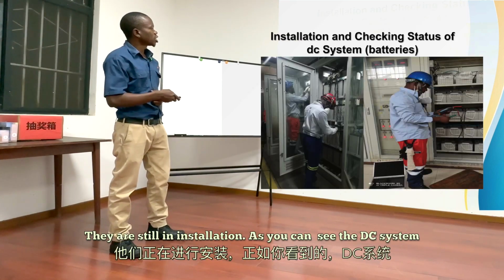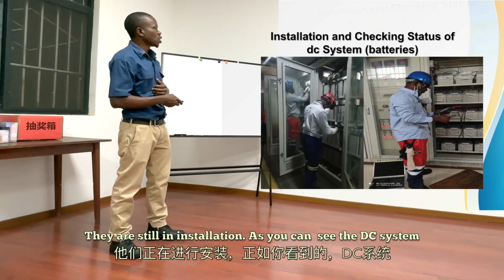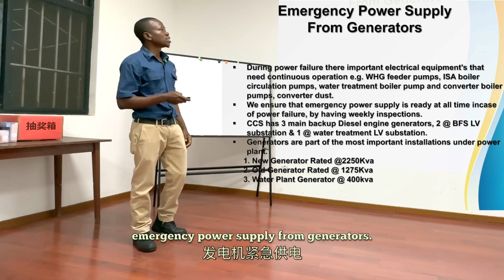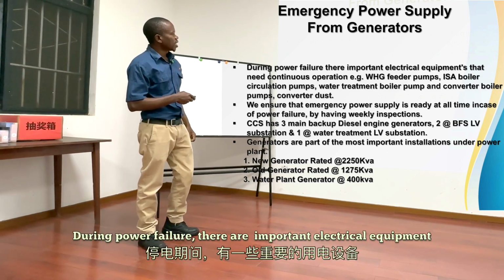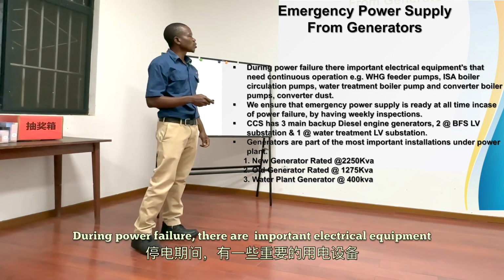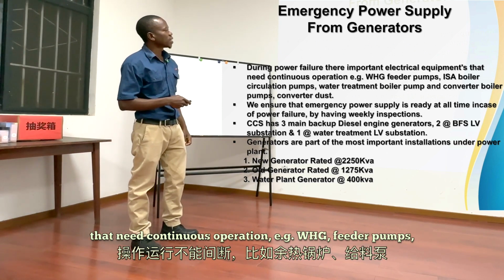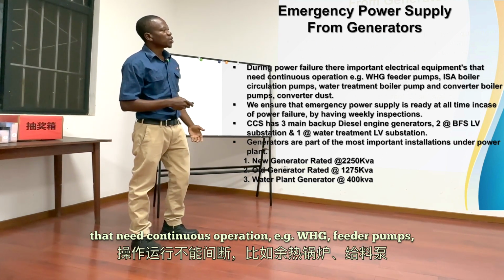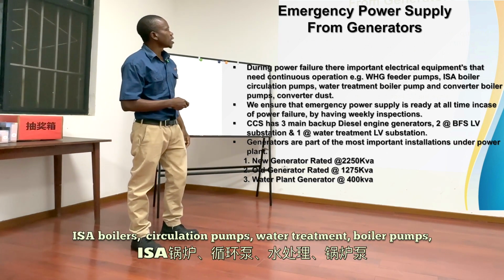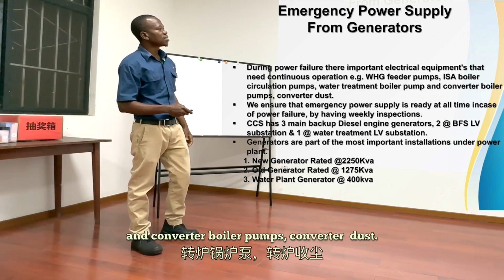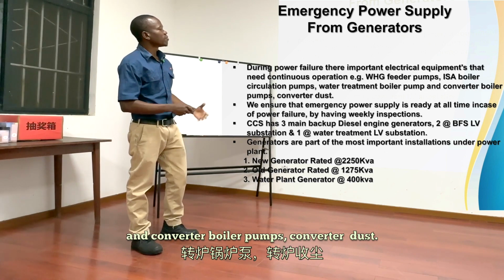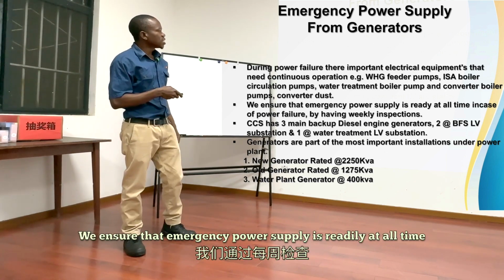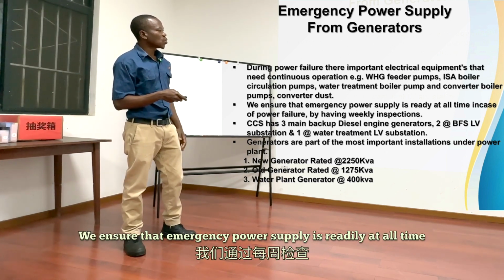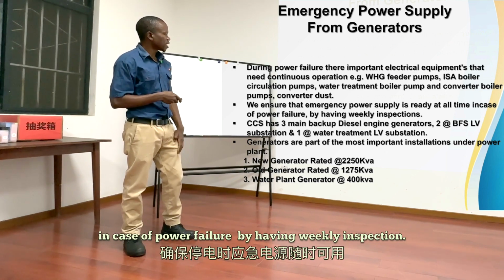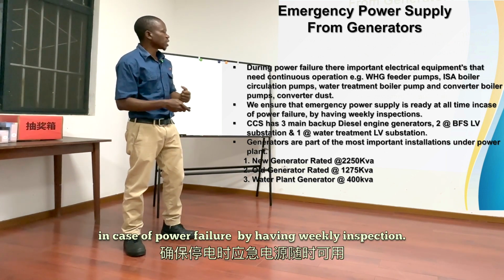Still on installation. As you can see, the DC system, emergency power supply from generators. During power failure, there is important electrical equipment that needs continuous operation, e.g., WHG feeder pumps, ISA boiler circulation pumps, water treatment, boiler pumps, and converter boiler pumps, converter dust. We ensure that emergency power supply is ready at all times in case of power failure by having weekly inspection.